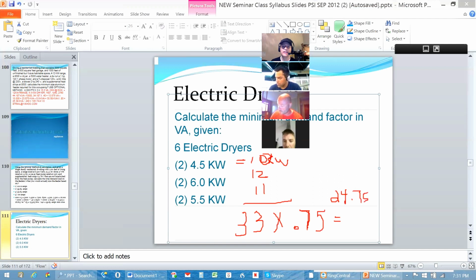Now, this is if I'm talking about the feeders, right? The phase conductor. I'm sizing a residential dwelling. I've got these 6 dryers, and I've got a bunch of other stuff, the square footage and the air conditioning, the ranges, whatever it might be. I would add all that together, and this 24,750 is just an amount that's added to the total overall demand load to size the feeders.